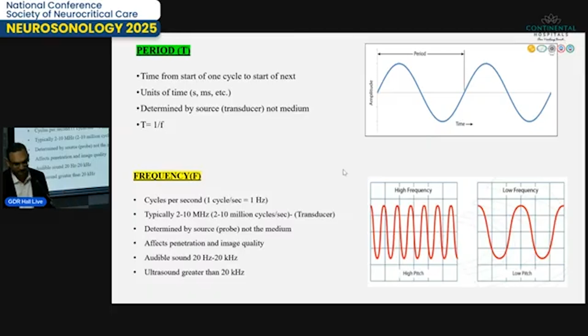Next comes frequency, which we normally discuss as high or low. It is cycles per second. One cycle per second is called 1 hertz. Typically, the probes we use for ultrasound have 2 to 10 megahertz, or up to 2 to 15 megahertz. Again, this is determined by the probe. It doesn't change with the medium. And frequency is most important, as it affects the penetration and the quality.